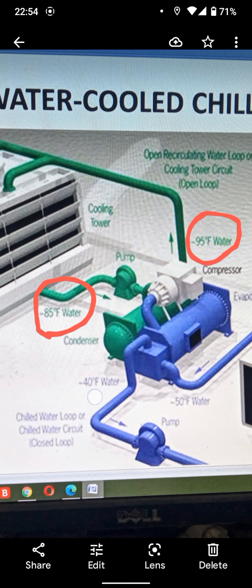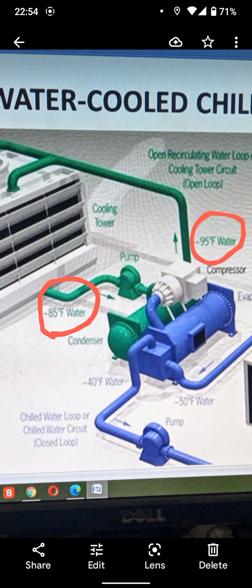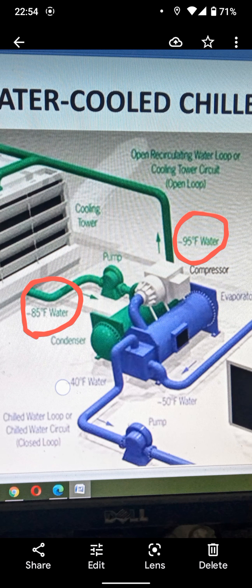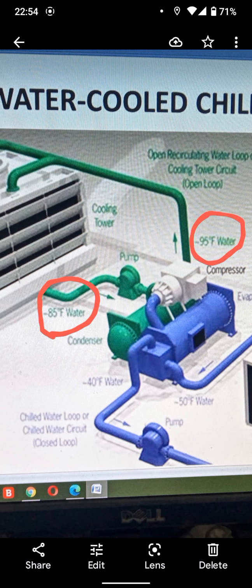Generally, people working on centrifugal chillers know very well that surging is caused by a condenser problem: condenser tubes blocked or scaled, or any problem from the cooling tower, flow problem, and so on. If there is scaling in the condenser tube, you have to use chemical circulation and descaling, then tube brushing, and this will solve the problem. Descaling and condenser cleaning solve the problem. And if you get the condenser approach to 1.5, I mean 2 Fahrenheit, the condenser approach is good.